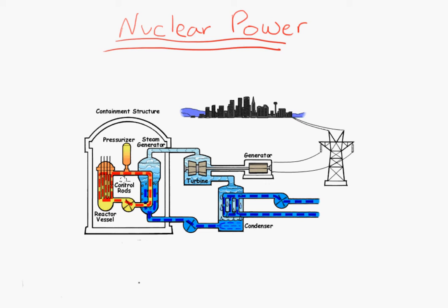As I mentioned earlier, we can either vary temperature or pressure to affect a change in phase. Well, since we know the liquid is very hot, we know we're going to have to do something with pressure to keep it a liquid. So we need to raise pressure to keep reactor coolant a liquid. And that's what the pressurizer does. Through a system of electric heaters and spray, we can control pressure in the pressurizer. And if we control pressure in the pressurizer, we can impact and control the pressure in the entire primary system here.